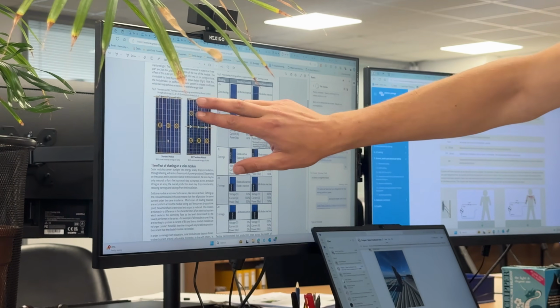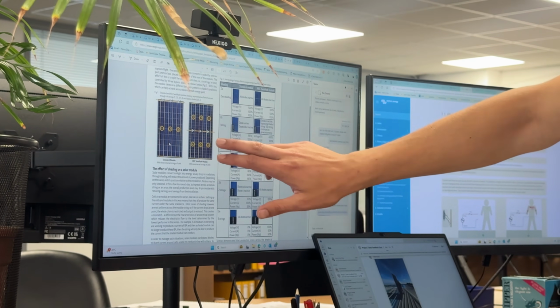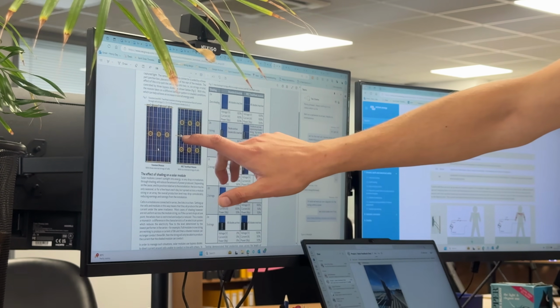In a lot of our design work, it makes sense to take the bypass diode layout within the panel into account in order to optimize for shade mitigation. It's important to pick a solar installer that understands the technology at this level, as that will have a direct impact on your system's generation and economic benefits.